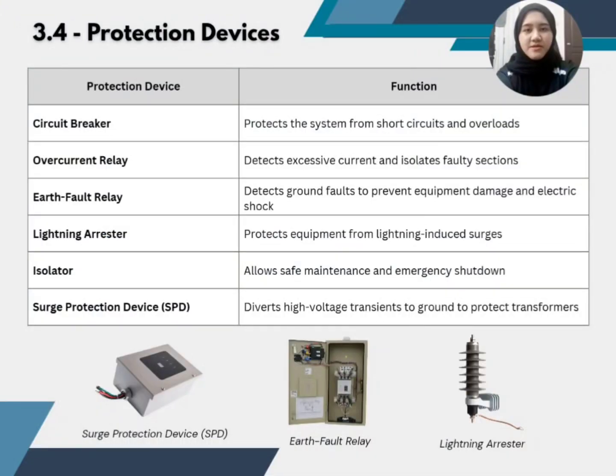Moving on to protection devices, the table shown in the slide contains a list of protection devices or equipment. Because safety is our top priority, we have implemented a multi-layer protection scheme. Circuit breakers and relays are installed to detect and isolate short circuits or overloads. And because this is an outdoor rural system, we also included lightning arresters and surge protection devices. These will protect our transformers and equipment from high voltage transients by directing them safely to the ground.